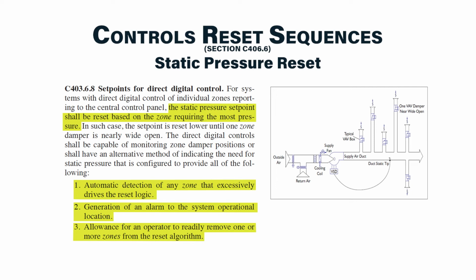In that sequence, VAV boxes are to send requests if they need more airflow, and the controller will trim the set point if there are no requests, and will respond quickly if requests start to come in, to make sure that there aren't any VAV boxes that are ever starved for air. Again, check ASHRAE Guideline 36 for a pre-written specification that you can quickly add to your design.